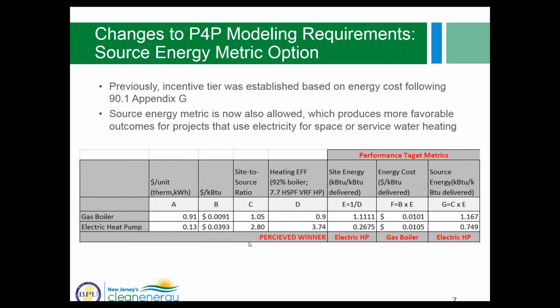And this table at the bottom of the slide illustrates the reasoning behind that. In New Jersey, electricity is very expensive relative to gas. So I checked the Energy Information Administration website for the last year. One therm of gas average cost was 91 cents. A kilowatt hour of electricity average cost was 13 cents. And if we convert into dollar per BTU cost to normalize for units, we see that electricity is almost 4 times more expensive than natural gas, BTU per BTU.